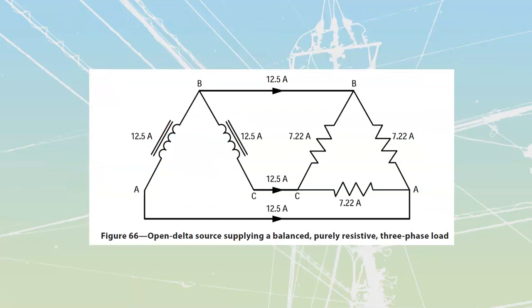Let's take a look at what this would look like inside of an open delta situation. In an open delta situation, we now have some limitations. Remember that before, we could look at combining two currents into a node over here. But now, all of a sudden, this whole section inside here is missing. There's no current to combine, which means the only current we could possibly get out is going to be the 12.5 amps. So my I line has dropped fairly significantly. My new I line is now going to be 12.5.